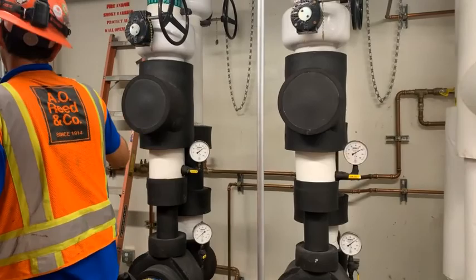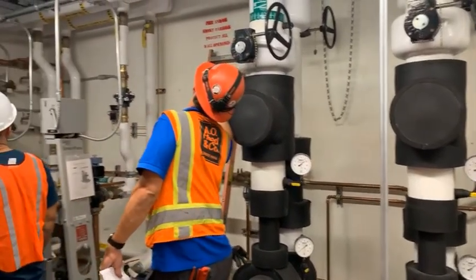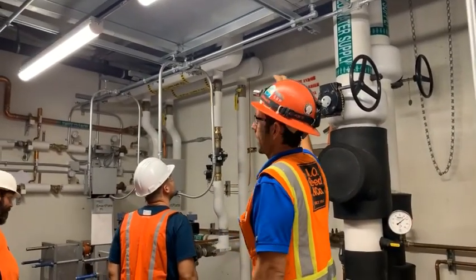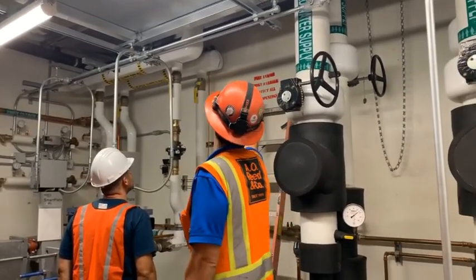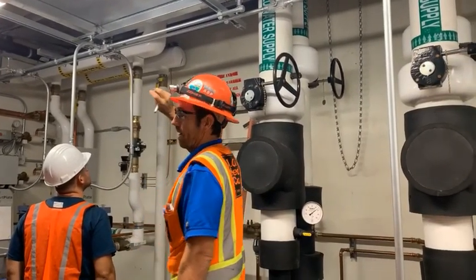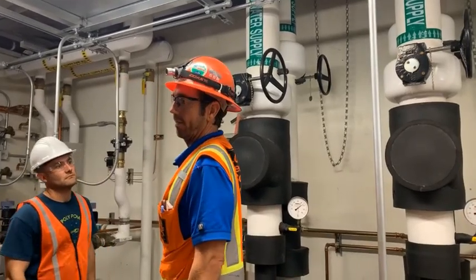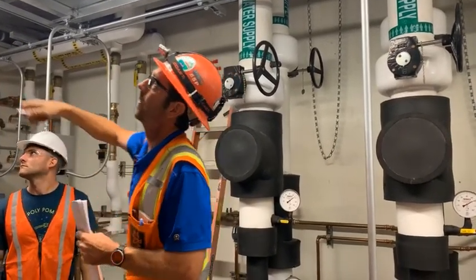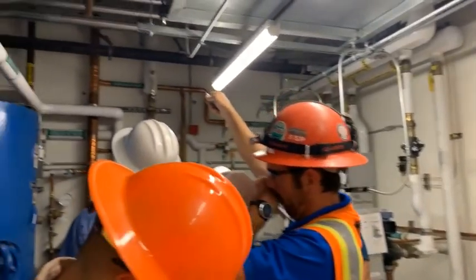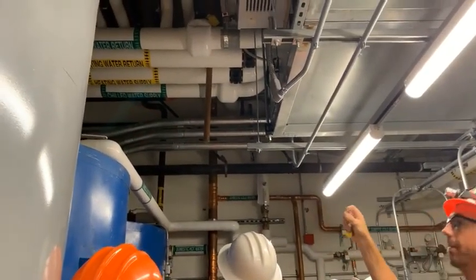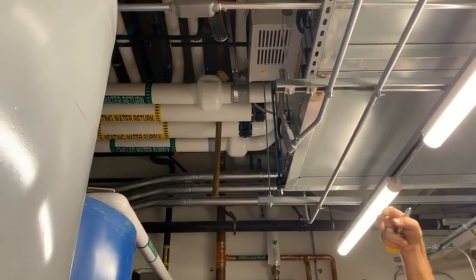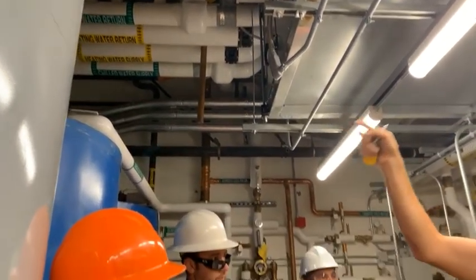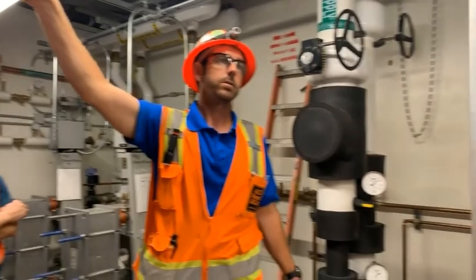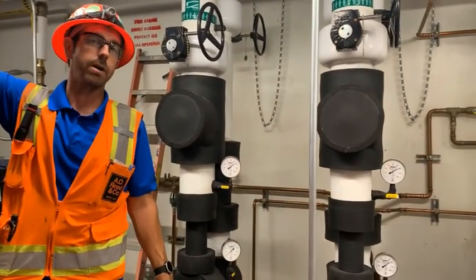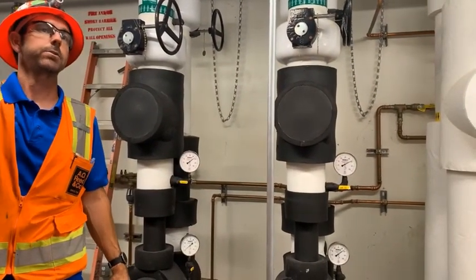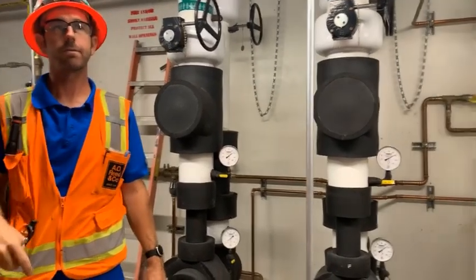There are extra shutoff valves up here in the ceiling. Supply and return for hot and cold. So there's 4 up here that will feed off, we call it segment 1 of the building, which is like to our right. And then there's 4 shutoff valves right up here. Excuse me. That will shut off what we call segment 2. Just know that your electric rooms are off of the segment 2 side, okay? So if you shut those 4 valves, or the 2 chilled water valves, you're going to be shutting off your cooling for the main electric rooms and the risers that go up. Okay, every floor has an electric room.